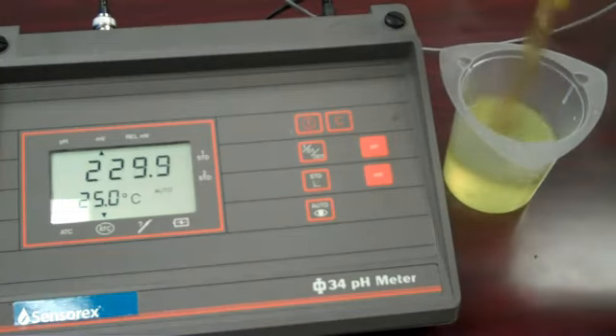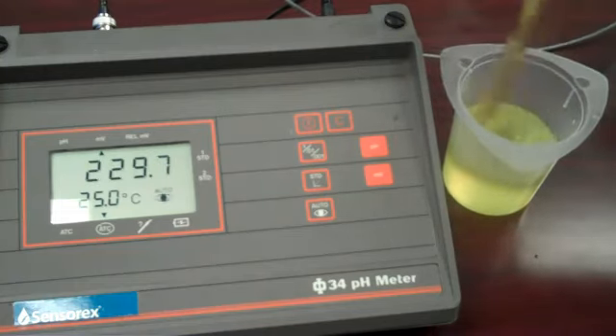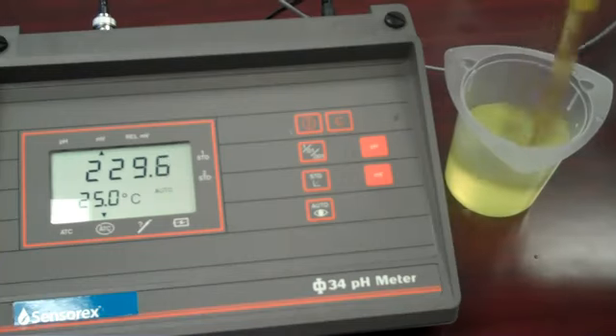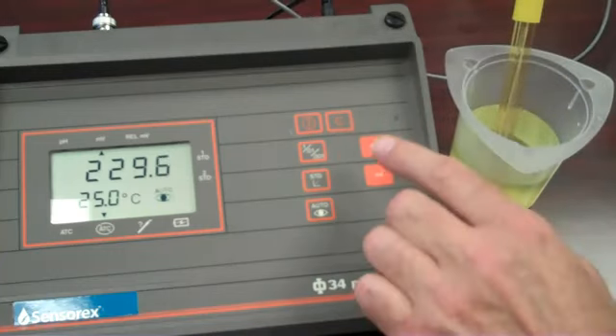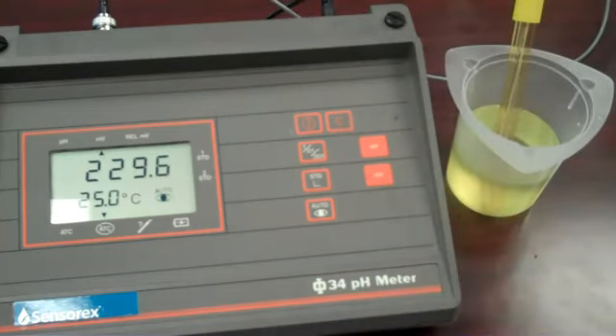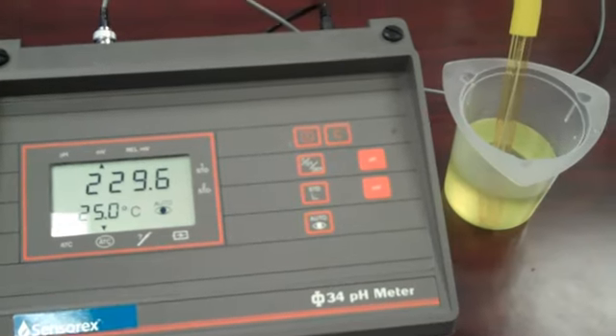Place the sensor into the ZoBell solution, giving it a quick stir for a few seconds, letting the readings stabilize. Make certain that your meter is reading on the millivolt scale. In this case, we're reading 229.6 millivolts, very close to the targeted 228 millivolts. For ORP, the tolerance is plus or minus 10%, so if you're within 20 millivolts of the target reading, you're doing real well. Some brands of ORP controllers actually require the user to program in two standardized ORP millivolt readings.